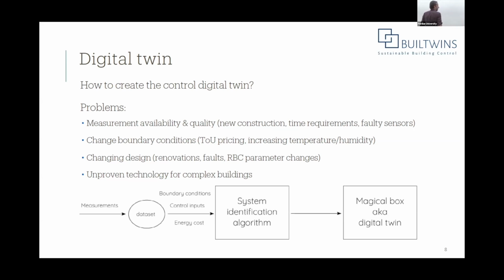Other things: the design can change. Quite often we have a hierarchical controller where there's an MPC on top and a rule-based controller below it, and the MPC gives set points to the rule-based controller. Now what happens if that rule-based controller suddenly changes? Someone changes a set point, the heating curve changes, or whatever—something changes in the rule-based controller, and suddenly your trained model, which you waited a year for, is out the window.